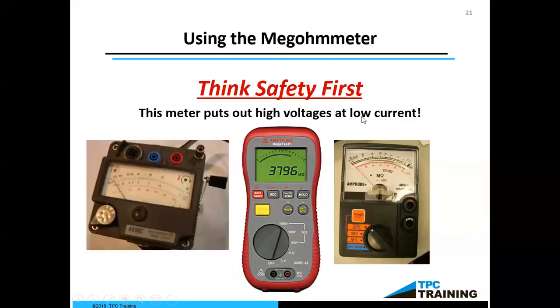If the insulation is not good, then we're going to have what we call a ground fault, and that would be a phase conductor coming in contact with our equipment grounding path, a very low resistance, a very high current is going to flow there, just like it does in a short circuit situation. So if we tried to start the motor under a ground fault situation, then certainly we would have something trip off or something explode or somebody get hurt. So we always want to make a good determination what the quality of the insulation on the windings are.